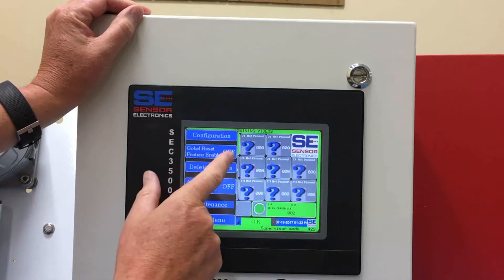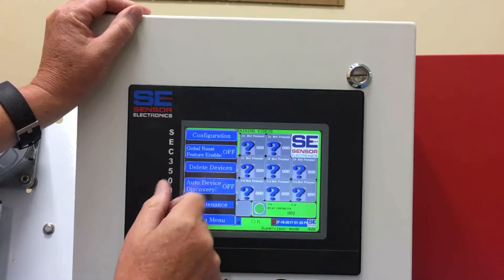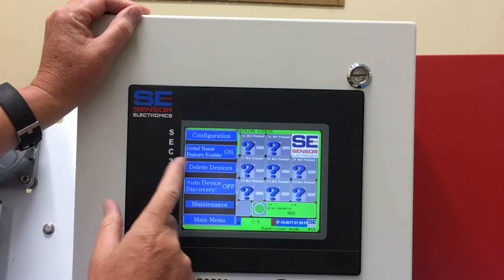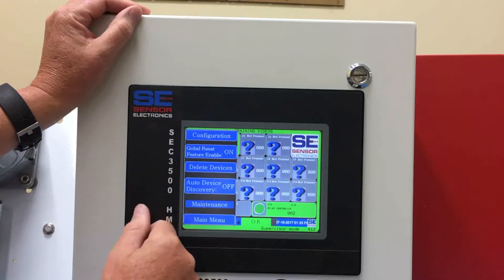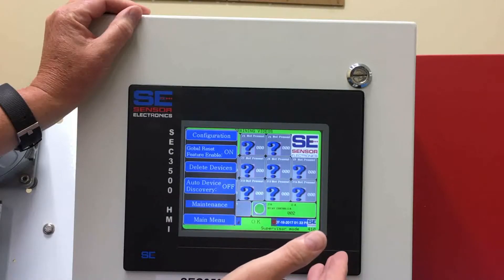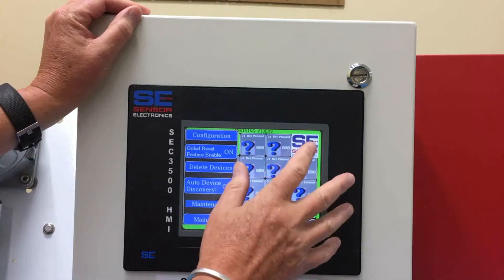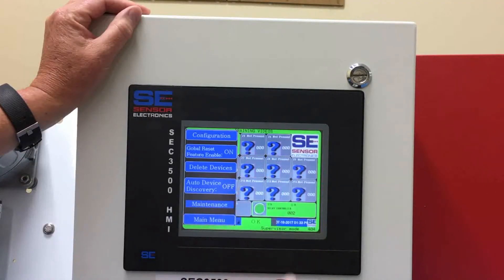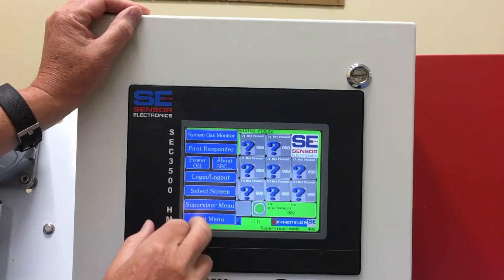Global reset is off or on, and your selection can be simply enabled by pressing on it. The global reset feature enables you to reset any latching relays in the system by pressing the reset relay button icon when it appears after you have an alarm and something has latched up.